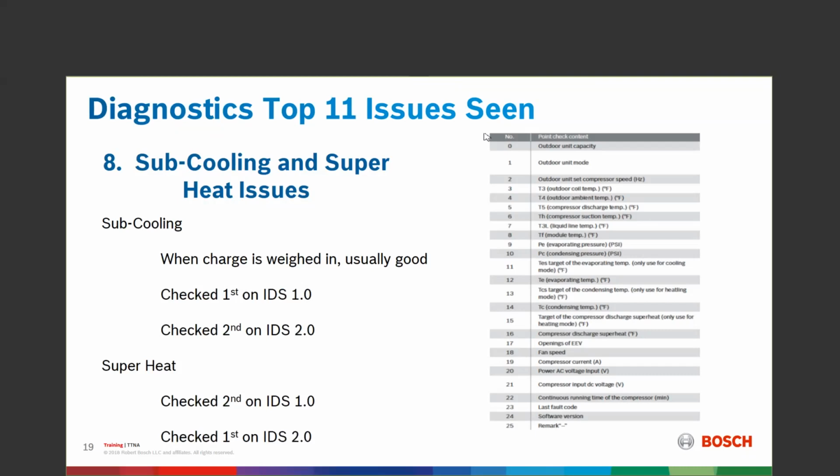How about suction pressure? I'm sorry, not suction pressure, superheat. Will it be low, the same, or high? The superheat will be high. I don't have enough refrigerant to keep a solid head of liquid up against the TXV. As a result, I'll probably drift a little bit. That's acceptable. We understand that with IDS 2.0 that there will be changes.